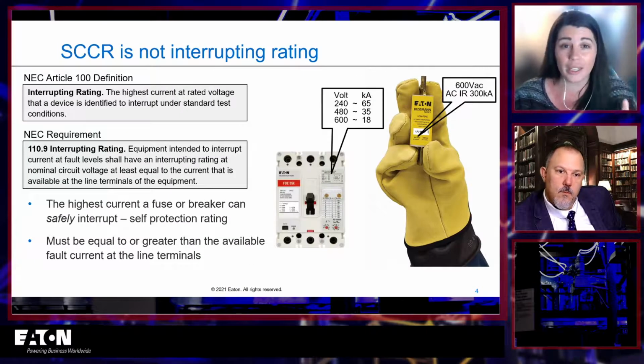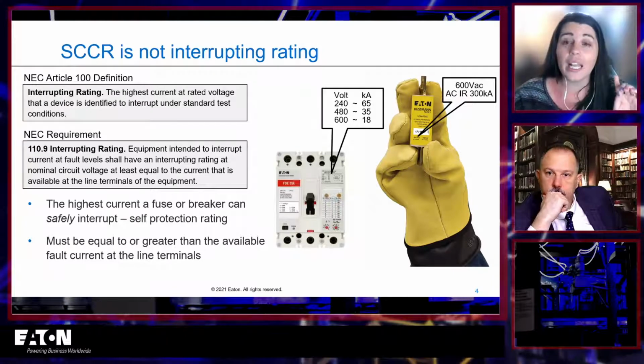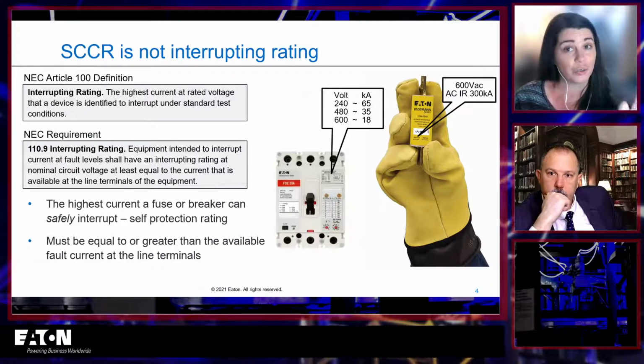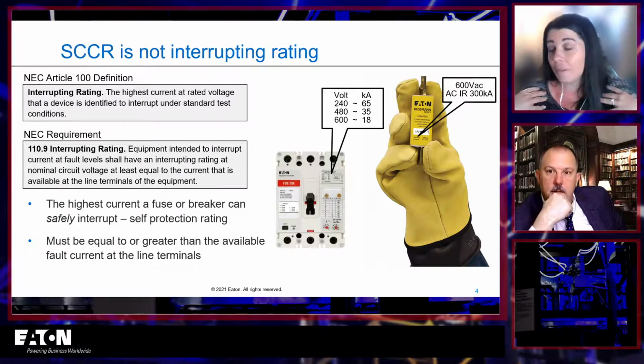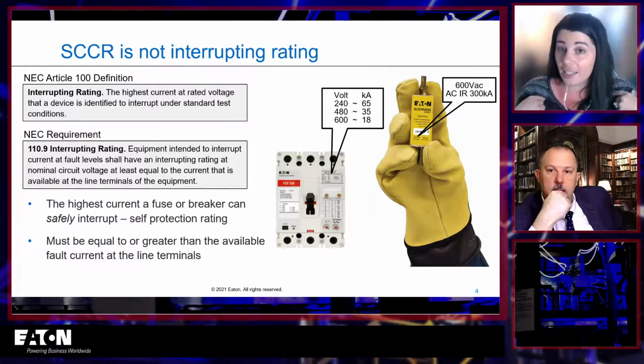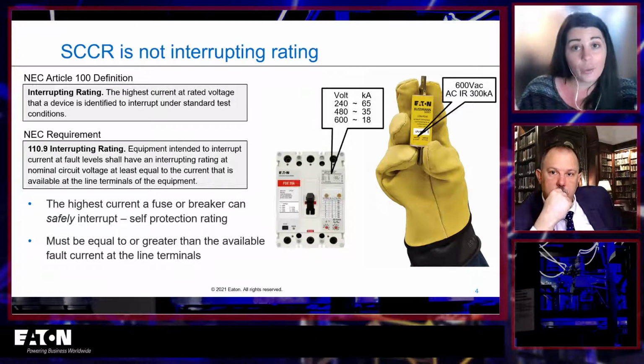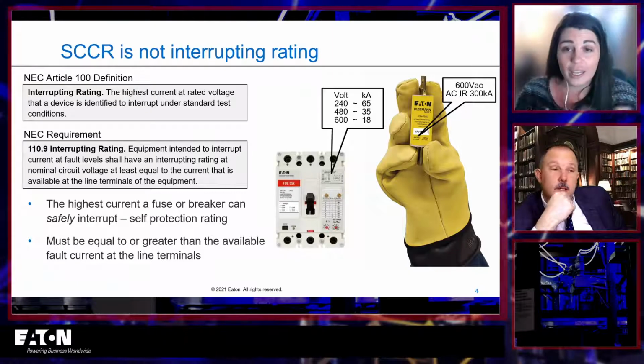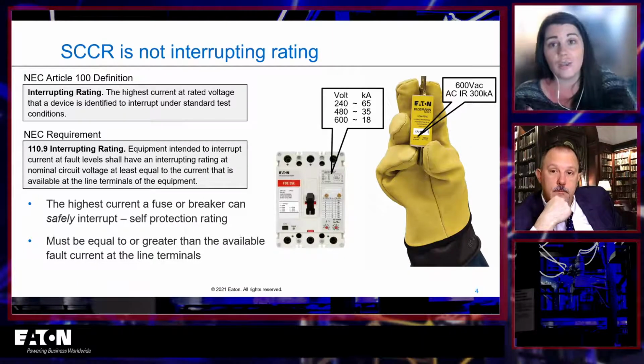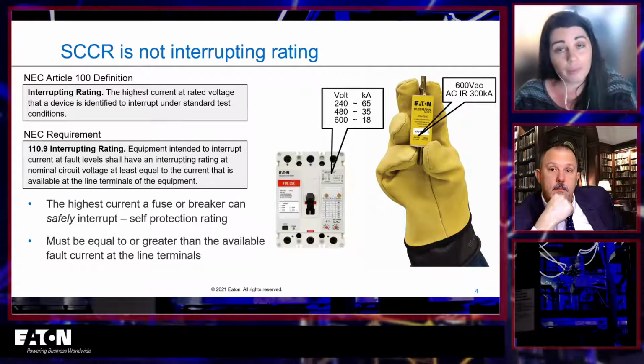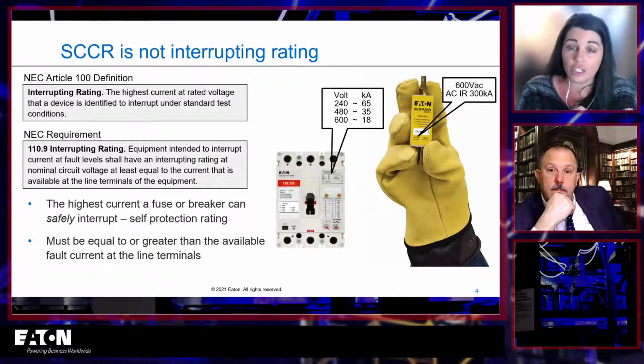Another very important thing to know about interrupting rating is that it is a self protection rating only. So if I'm a breaker and I have a 35,000 amp interrupting rating, it means me, the breaker, if I see 35,000 amps, I will trip, I will open the circuit, and I will be okay at the end of it all. But I'm not guaranteeing the protection of anybody around me. That's actually when we get into SCCR. SCCR has to do with the entire assembly. Interrupting rating is just a rating for that breaker or for that fuse.